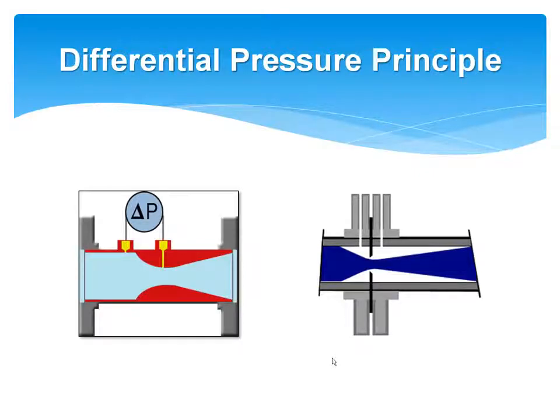The differential pressure principle is basically you're putting an obstruction in the flow stream and measuring the pressure upstream and the pressure downstream, and then the flow rate is a function of the square root of that differential pressure measurement. Again, this is a good, robust technology. It's been used for many, many years. It does have some good benefits. These types of meters, certain versions of them, may not be as susceptible to straight runs of pipe. It is fairly difficult to measure a wide range of flows because of the square relationship between differential pressure and flow rate.